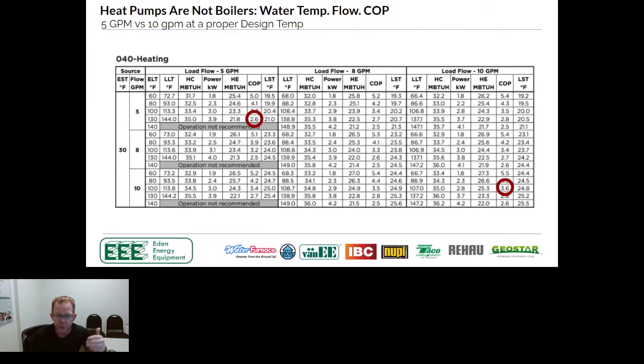But at that COP of 2.6, if we go back to my comment earlier, if we design around the proper flow rate, which is 10 gallons a minute, we go from a COP of 2.6, or 260% efficient, to 3.6. And that's a huge difference. So we want to make sure that when we're looking at these units, we're paying attention to what we're doing with the unit. The other thing that's worth noting is you can actually see the capacity. I'm just moving my mouse around it by the 5 gallons a minute. You also have that capacity issue we talked about. So this particular unit, when I've got 5 gallons a minute going through it, is extracting 21,000 BTUs, whereas just by increasing the flow rate to the unit, I'm now extracting 26,000 BTUs out of that unit.